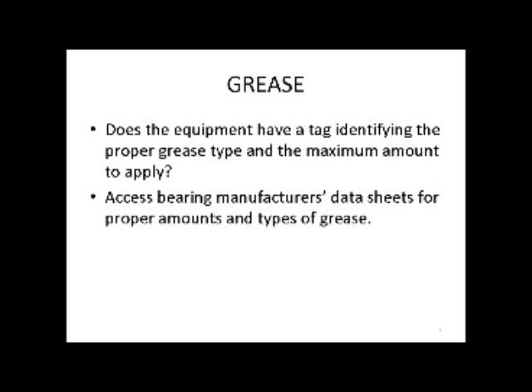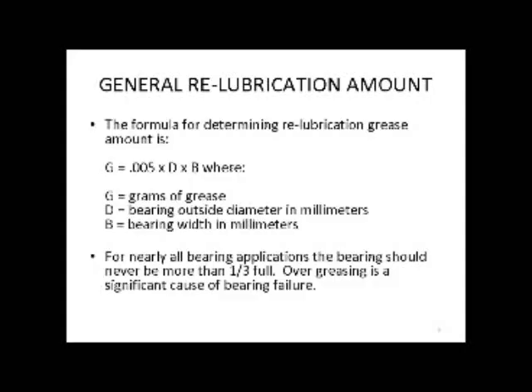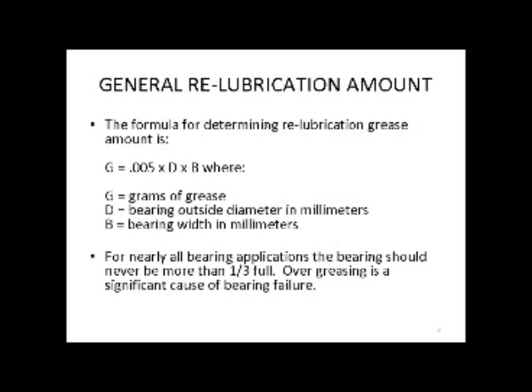In greasing, does the equipment have a tag identifying the proper grease type and the maximum amount to apply? Access bearing manufacturing's data sheets for proper amounts and types. When we first started this journey, none of our equipment had this — absolutely not one piece. The formula for determining re-lubrication grease amount is: G = .005 × D × B, where G is grams of grease, D is the bearing outside diameter, and B is the bearing width in millimeters. A general rule of thumb is no more than one-third full.